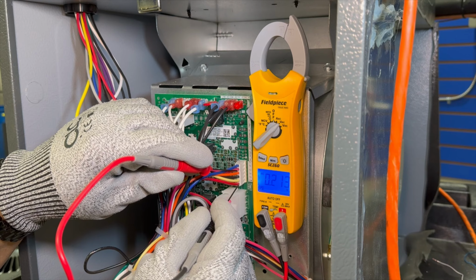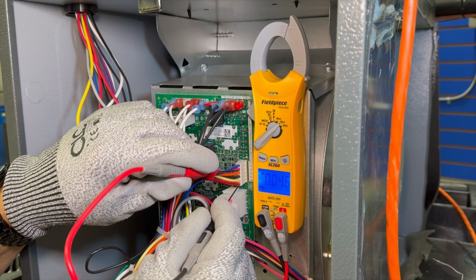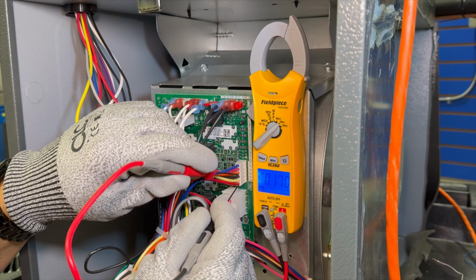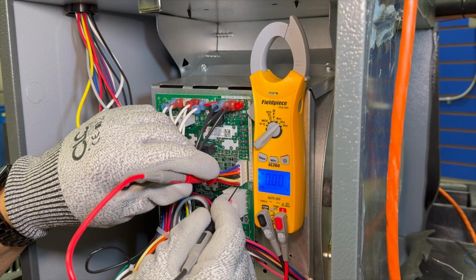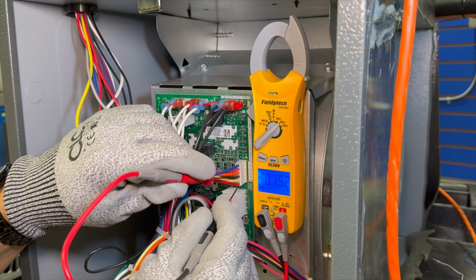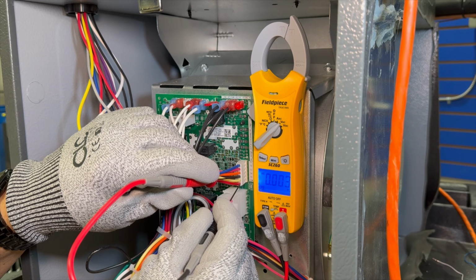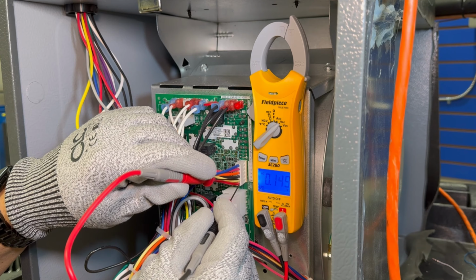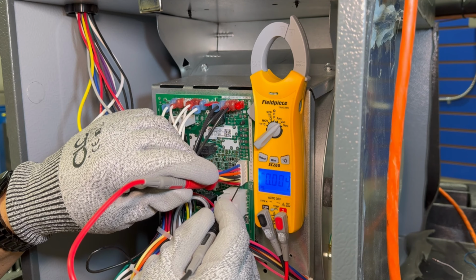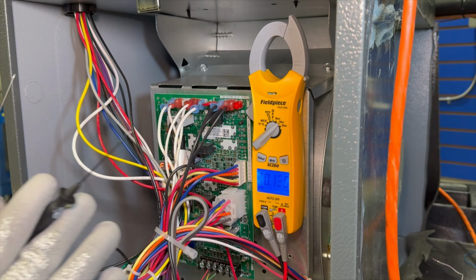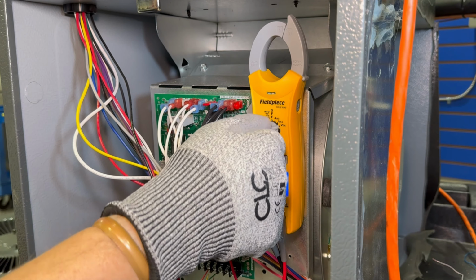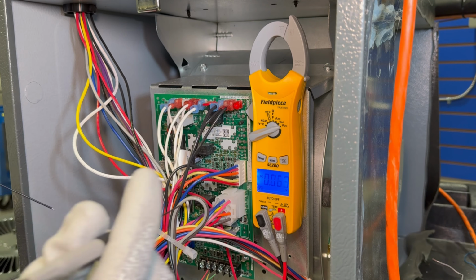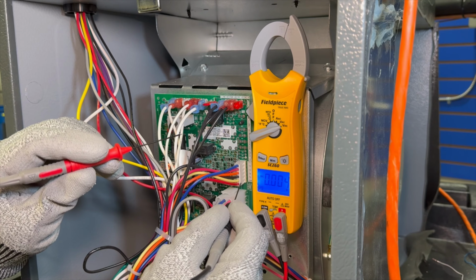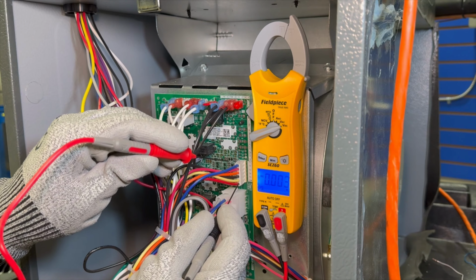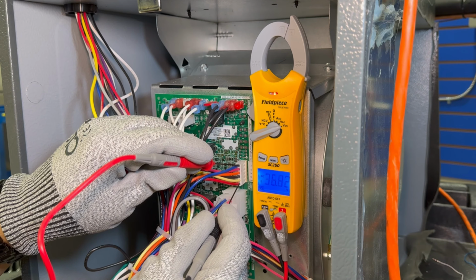Not true. So we could check through the other terminals and we'll see that there is no AC voltage on the other fan speeds. But what we're actually looking for on this particular manufacturer's board is a DC voltage for the fan control of our ECM motor.